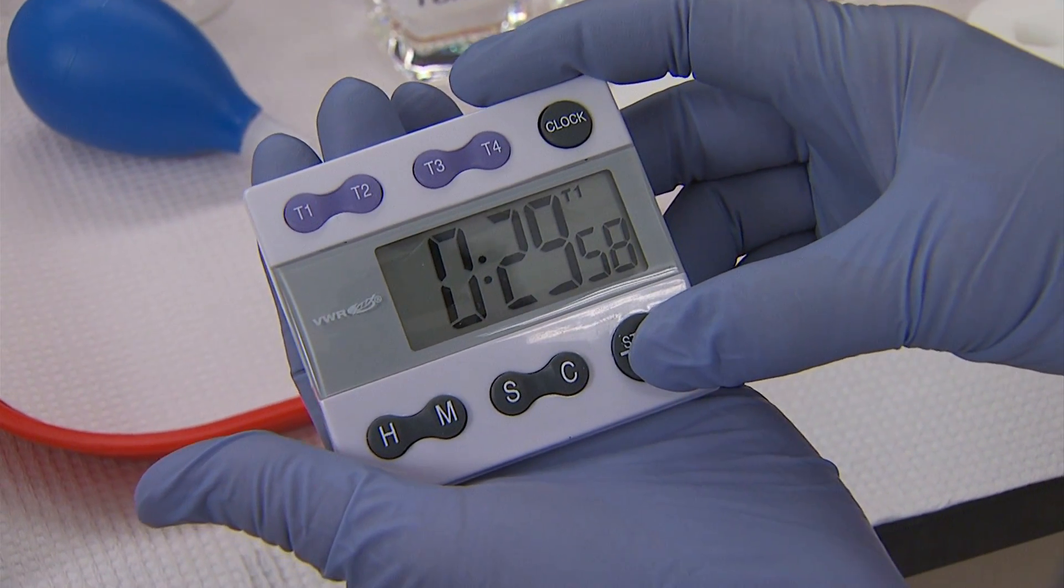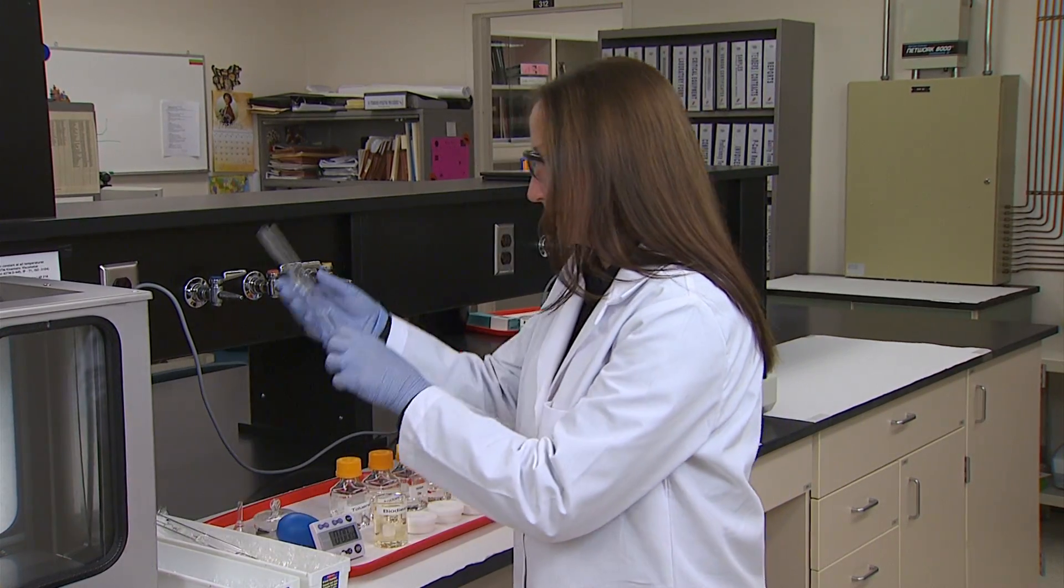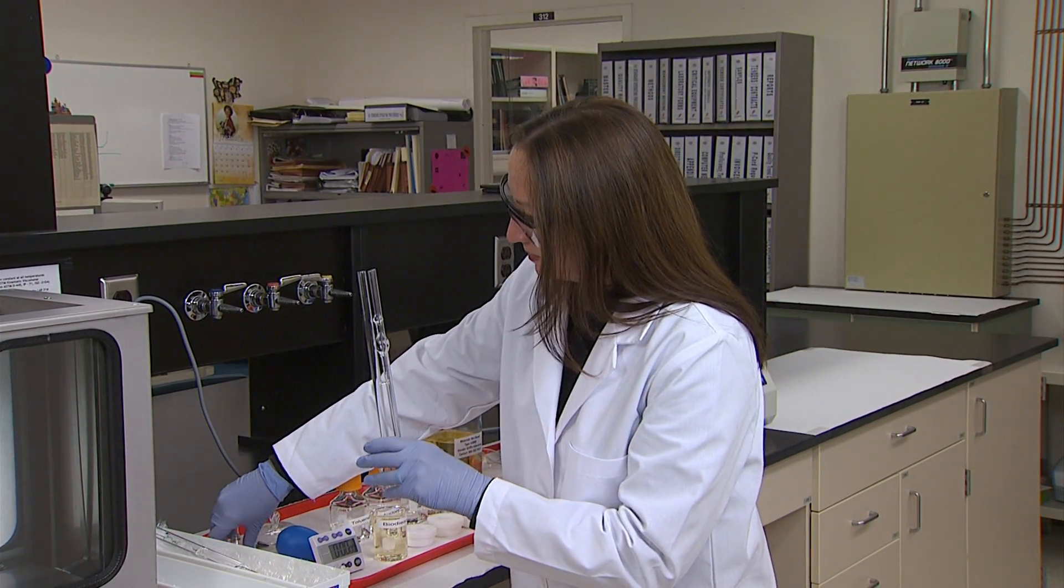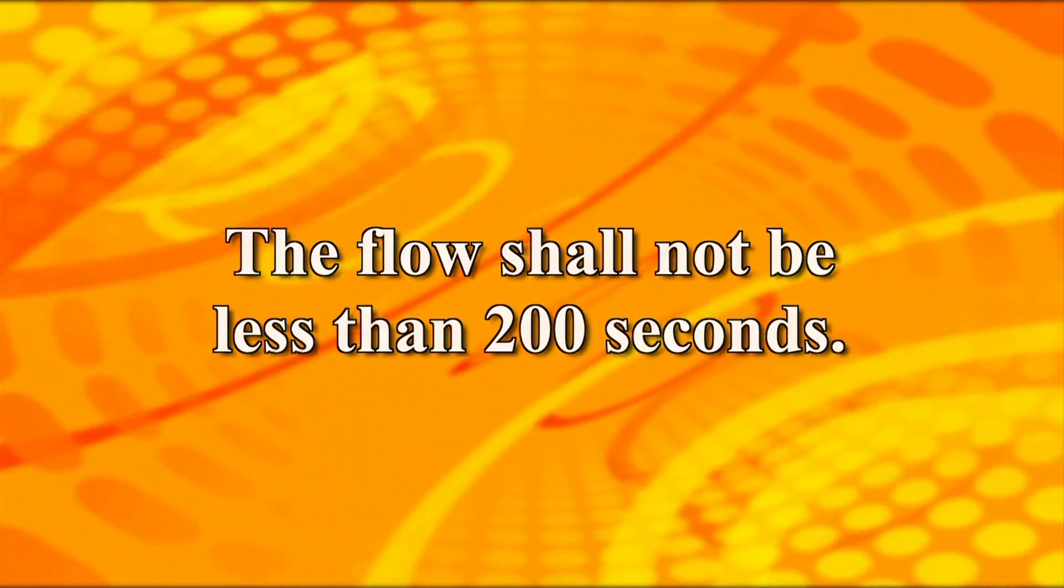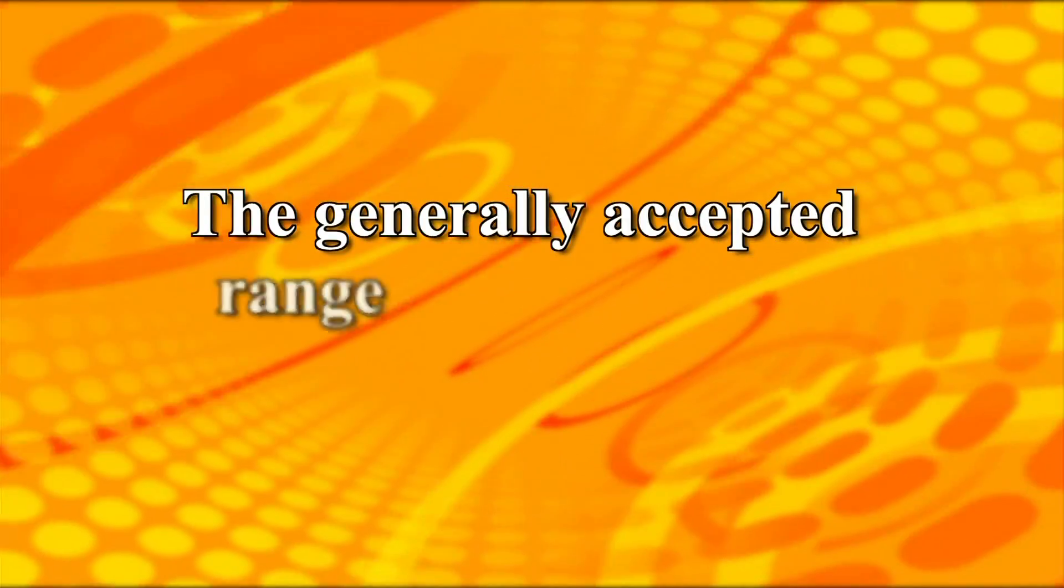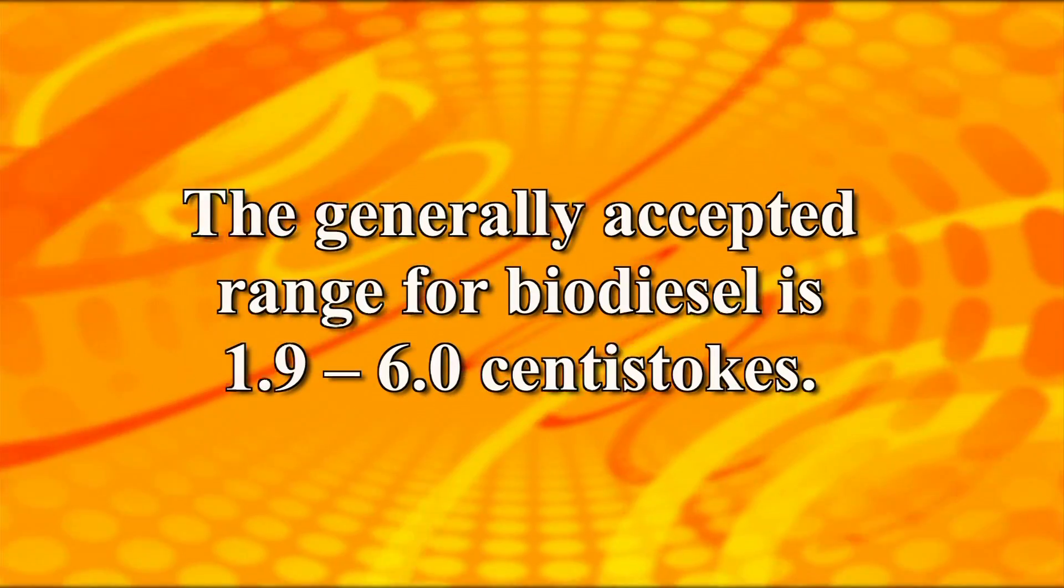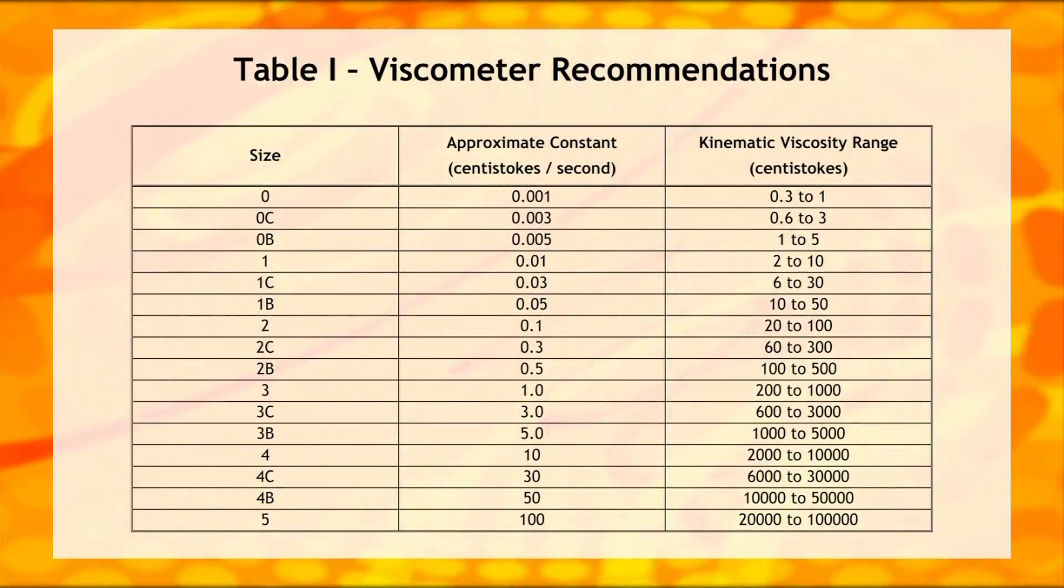To analyze a standard or sample, select a clean, dry, calibrated viscometer having a range over the estimated kinematic viscosity. The flow shall not be less than 200 seconds. The generally accepted range for biodiesel is 1.9 to 6.0 centistokes, so a number one viscometer may be a good choice. Refer to table 1 for specific viscometer recommendations for the expected viscosity range.